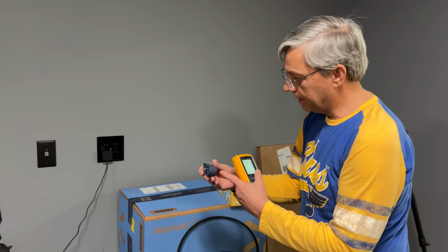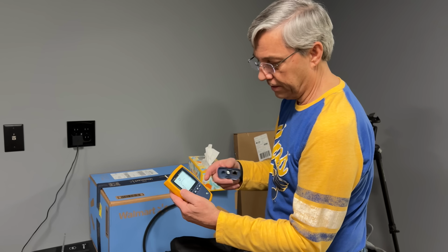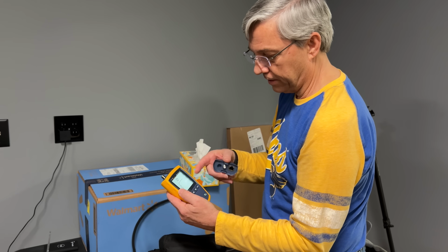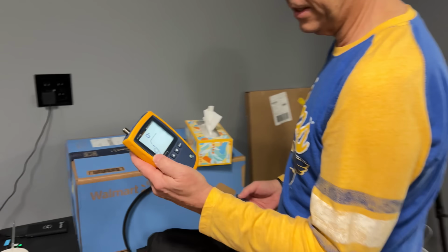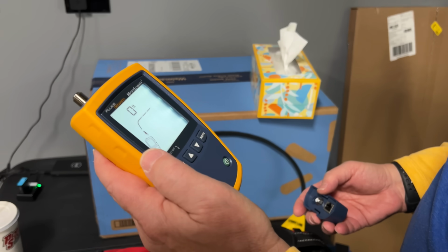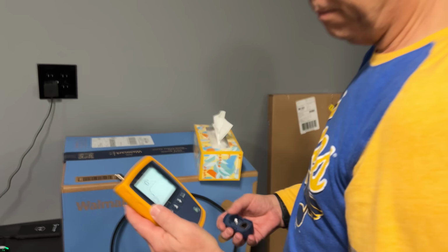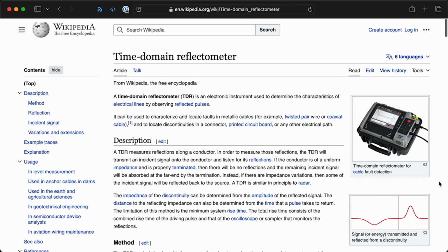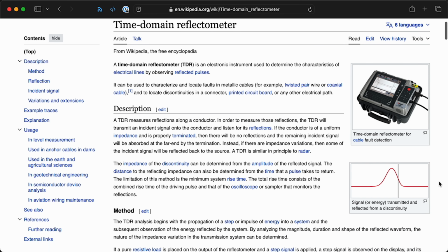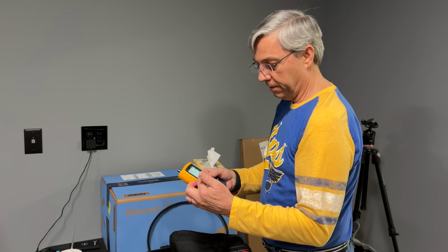So this is ID1. Go back, it'll tell you ID1 how many feet it is and all the connected wires, whether they're connected correctly. How does it know how many feet the wire is? It's not going in there with a measuring tape. Yeah, it does that magic transmission, TDR type stuff, so that it can tell where the fault would be too.